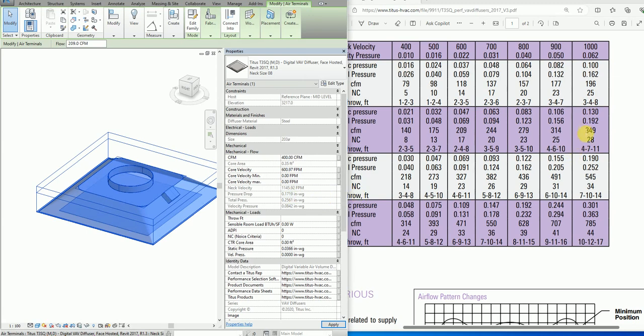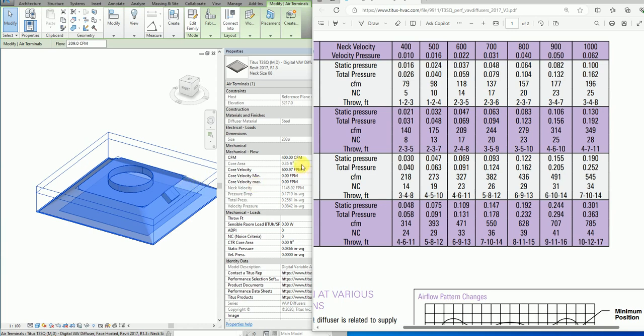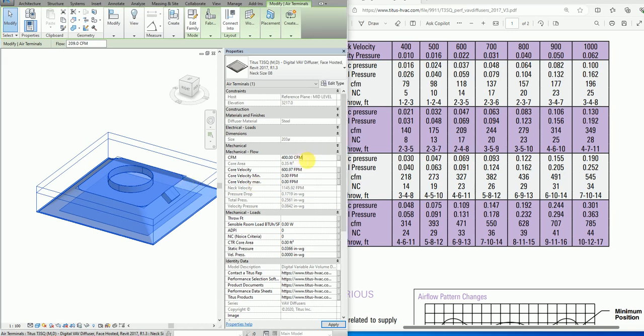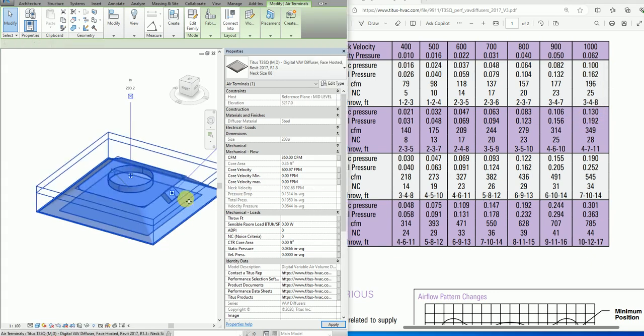Let's say if I put 400, it's going to give me something more than 0.13, which is here 0.17. If I change it to 350, which is 349, the static pressure is 0.13, which is 0.1314.